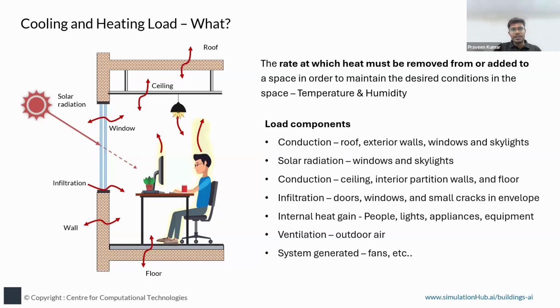There are different load components that contribute to the space cooling and heating load. I have combined both cooling and heating loads. The components include conduction of heat through roof, exterior walls, windows and skylights. The second component is solar radiation that enters the space through windows and skylights. The next is conduction through adjacent spaces or interior partition walls, ceilings, and floors. Then infiltration that enters through doors, windows, or small cracks in the building envelope. And the next component is internal heat gain, that is from people, machines, appliances, and lighting, which also add heat gain into the space.